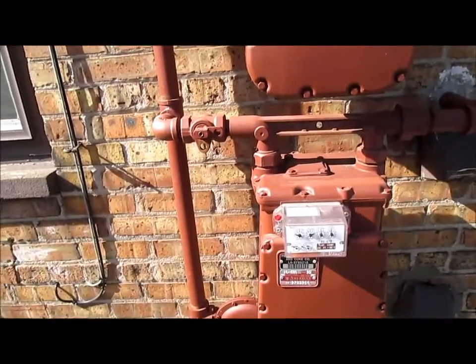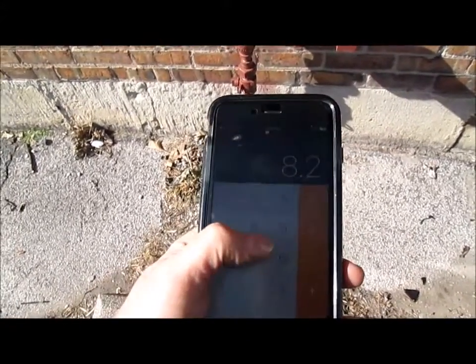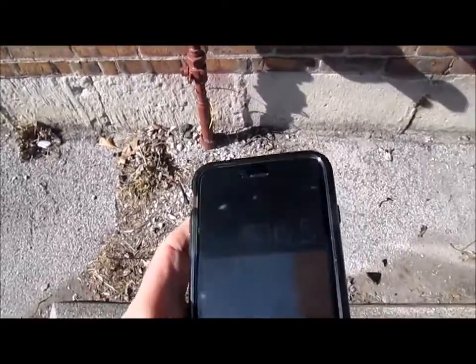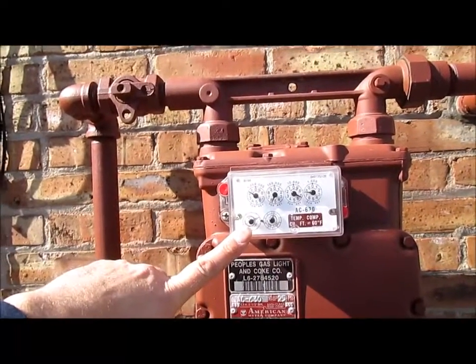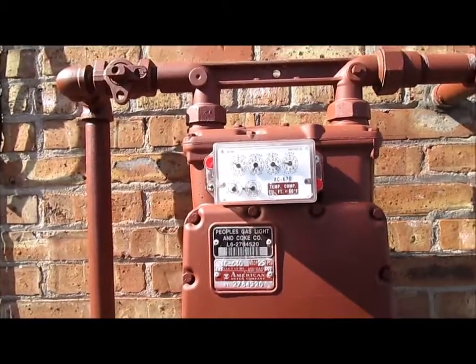Now that is a half-foot dial — focus in on that, it's a one-half foot dial. So if we went around 8.25 times on a half-foot dial, that would be 4.125 actual feet per meter. But because we have two meters spinning at the same speed, we have 8.25 feet per minute total.